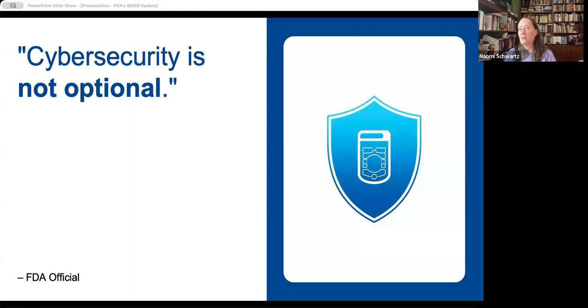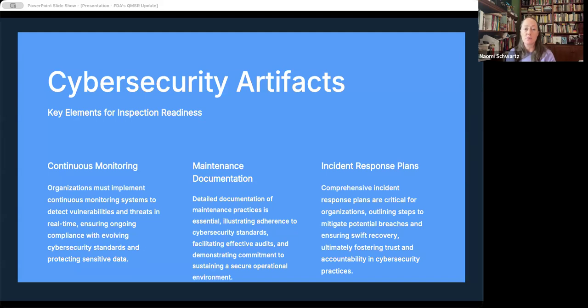In short, as we have heard multiple FDA officials say in public meetings, cybersecurity is not optional. You really have to think about how it's integrated into your quality management system systemically and make sure that all of those elements that we talked about are covered in terms of your cybersecurity behaviors. That means continuous monitoring, detecting vulnerabilities, detecting threats to the extent possible in real time for systems that are networked, having a network intrusion detection or network intrusion protection system in place to alert a user, danger, Will Robinson, something is going wrong, right? As much as possible, letting people know actionably in an appropriate time frame to stop doing something if it's causing a problem or stop using something because it's under attack.